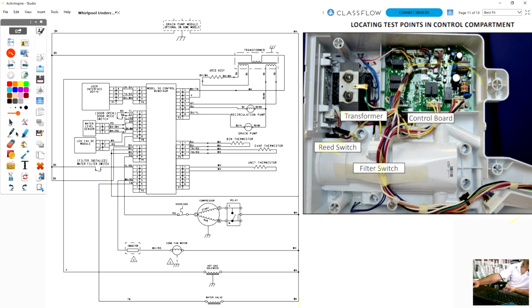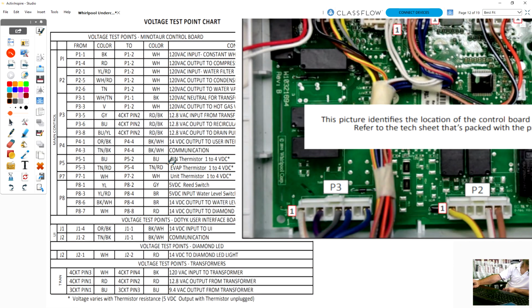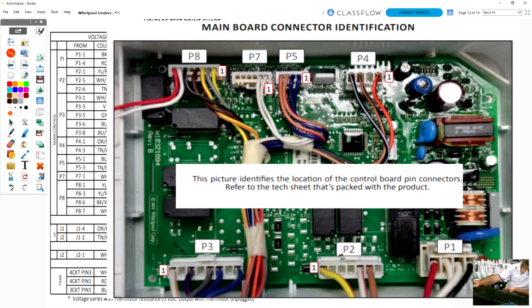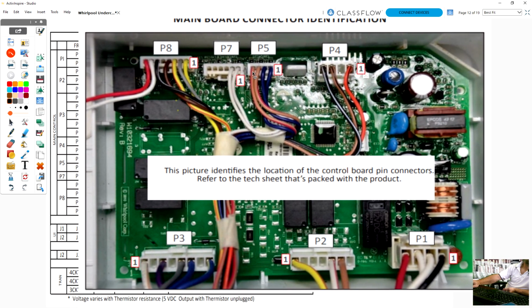To test that, we can look at the board here, and we can see the evaporator thermistor goes to plug P5, pins 3 and 4. That's these two tan wires right here. I can make two different tests from the board for this. One, I can check the voltage and see if I have the 5 volts coming off the board. And two, I can unplug this and put my meter leads on these two wires and ohm out the resistance of my thermistor.